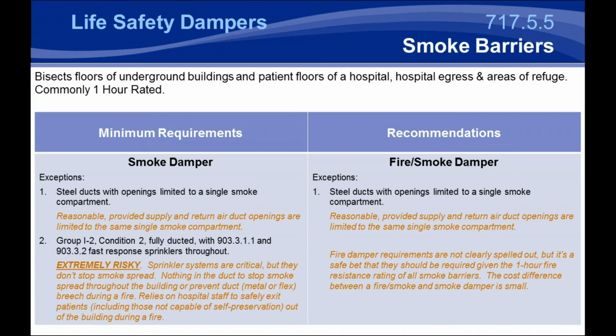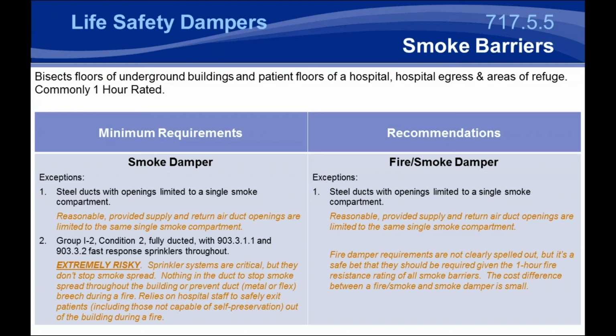Now, of course, in other types of occupancies, where steel ducts are limited to a single smoke compartment, we think it is a reasonable trade-off that smoke dampers are removed because basically the supply and return openings are limited to the same compartment and smoke will not get out of that compartment to other areas of the building.